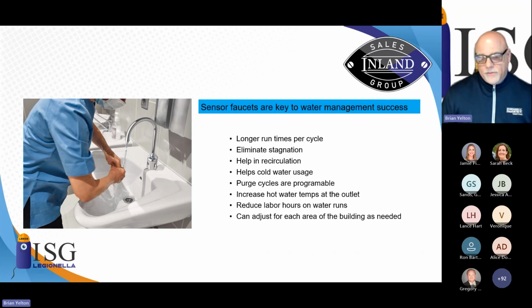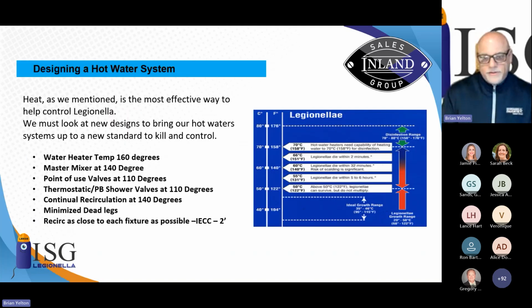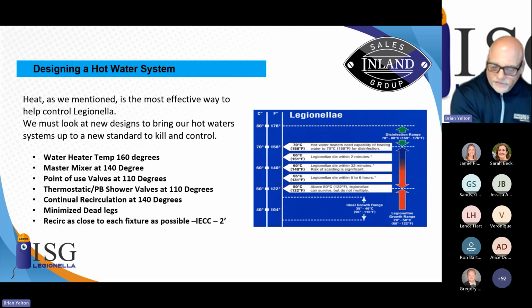We're going to increase our hot water temperatures throughout the building, making sure we're doing all these types of things. When we look at designing a hot water system, this is the gold standard we're trying to achieve today: hot water temperature at 160 at the source, master mixer at 140. We'll recirculate that water at 140 degrees throughout the entire building, use point-of-use valves when needed at 110, and use thermostatic and pressure balance shower valves set at 110 or below, whatever you want them to be.